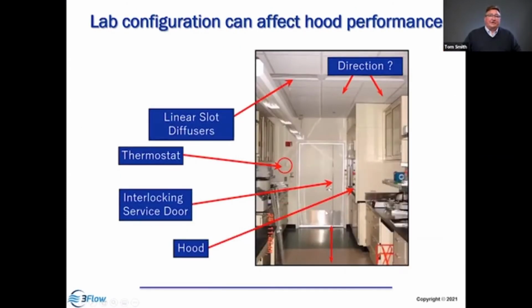Looking into a laboratory again, we see a couple of issues here. This hood is located right on a traffic aisle near a door, so that's going to cause some issues. The supply diffusers are blowing directly at the hood, so that could be a cause of cross drafts. And the thermostat's located way over here, so by the time the temperature changes, it may be going through cycles of cold to hot, cold to hot. And because of this door being close to the hood, we had to put an interlock on it so that people couldn't go in or out that door when the sash was open. They had to use the secondary egress route.